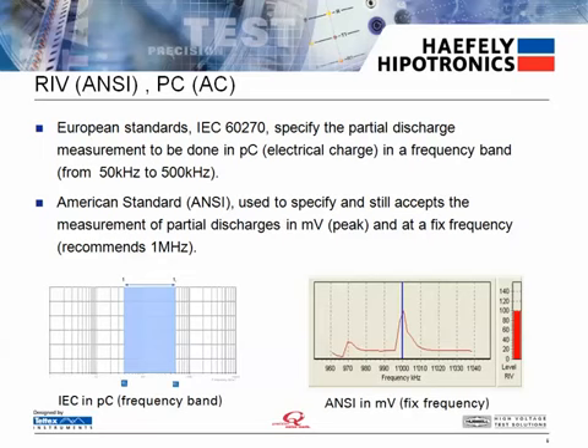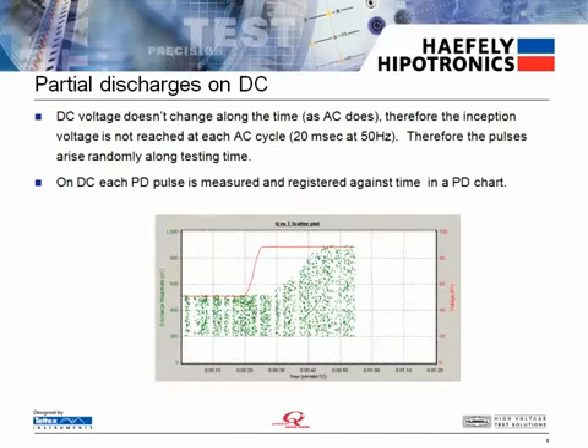There are two main standards for measuring partial discharge. The first being the IEC standards, which specify partial discharge to be measured in pC or electrical charge within a frequency band. The other being the ANSI standards, which specify partial discharge to be measured in millivolts or peak voltage at a fixed frequency. One can also measure partial discharge on DC voltage. DC partial discharge measurements are specified as a number of pulses over a given pC level over a given time period.